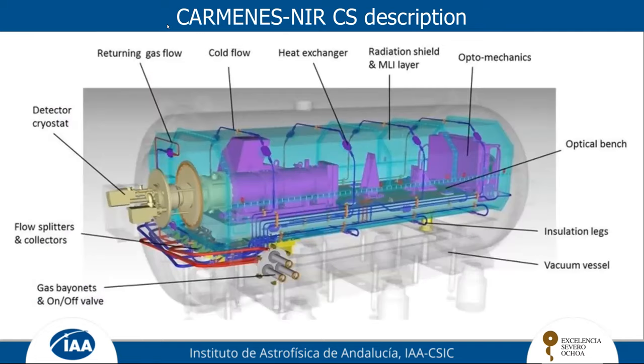Okay, it's because the team selected a working temperature of 140 K. If you work with liquid nitrogen, you are working at lower temperatures—basically, that's the concept. It's also because ESO participated in the design of this cooling system and wanted to try the same concept used for the detectors, but they wanted to make sure it also worked well with the instrument. In the end, it was quite harder than just for the detectors. But basically, it's because of the working temperature. Other instruments use liquid nitrogen for the detectors and also for the whole instrument, but that's because they are working at lower temperatures.